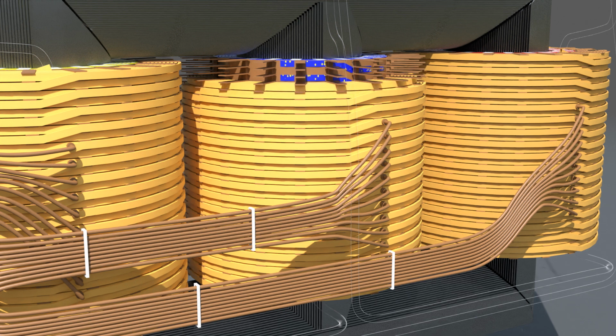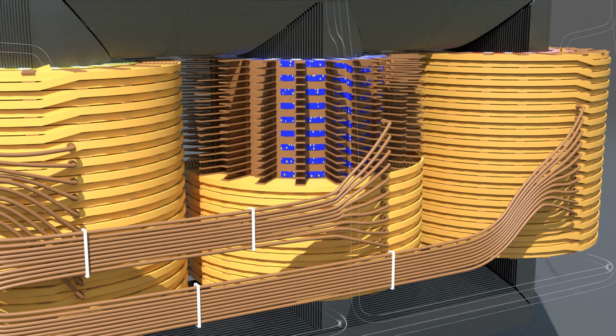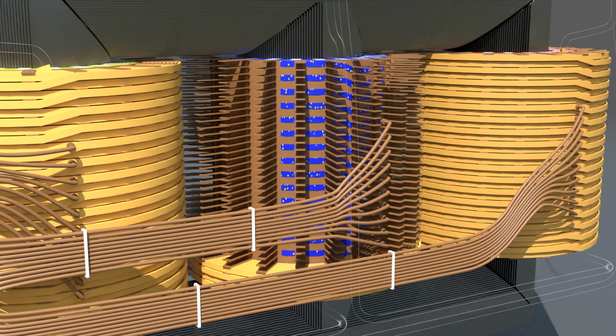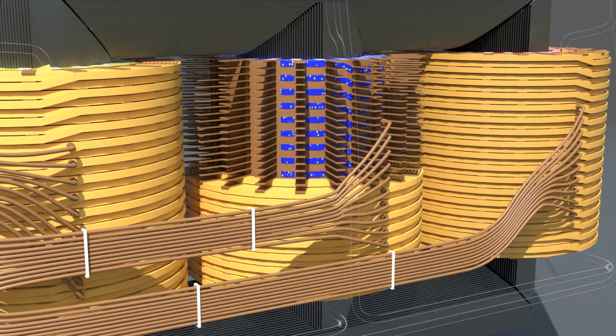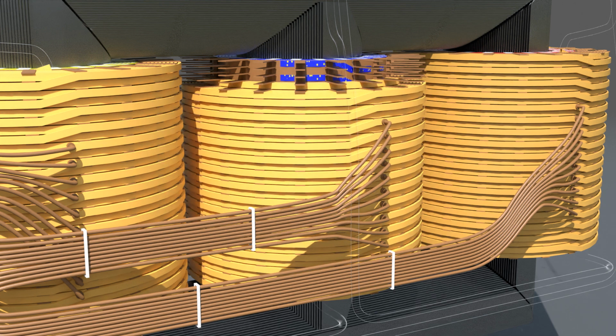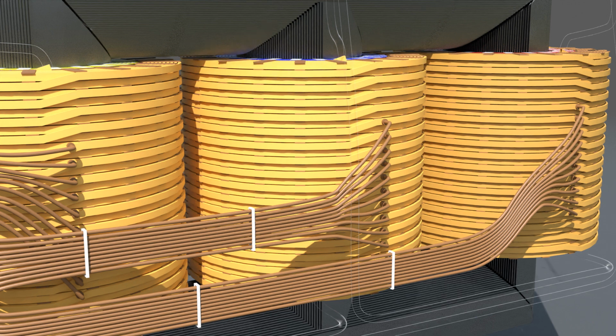The tap positions in a transformer are connected to the secondary winding through different points along the winding. By changing these points, the voltage output is adjusted. In on-load tap changer, this happens automatically to maintain a steady voltage.